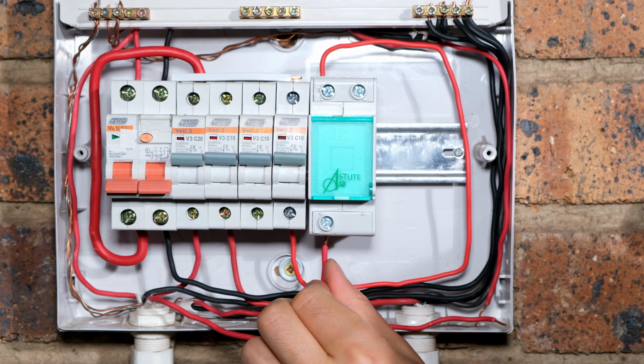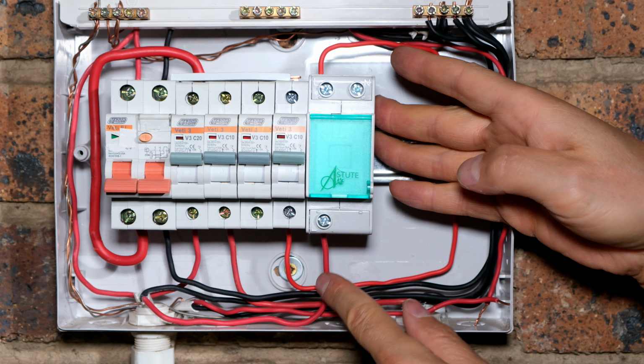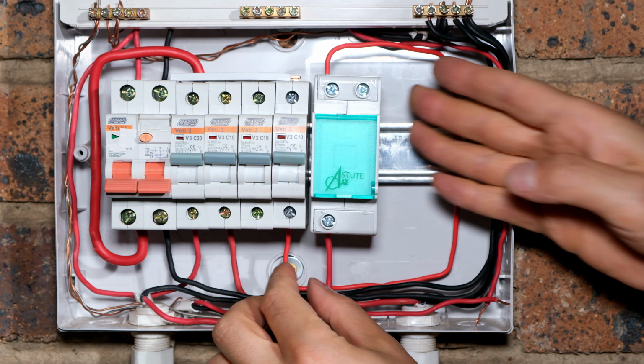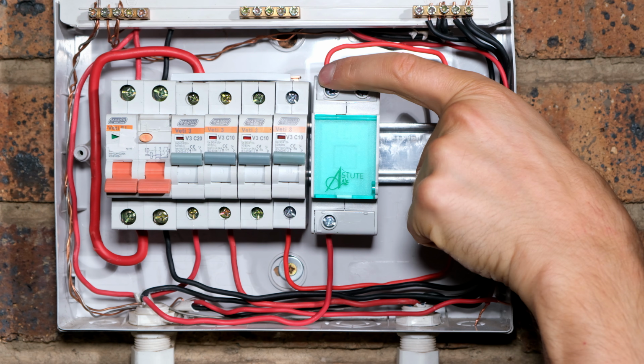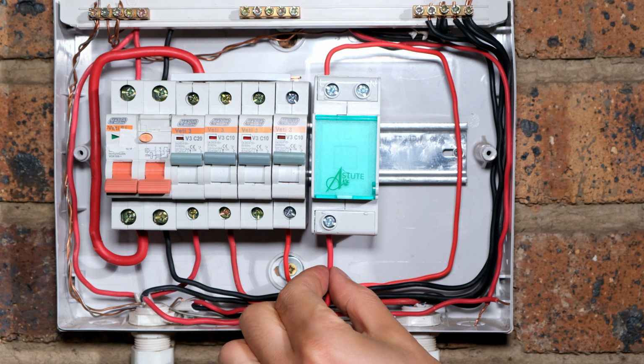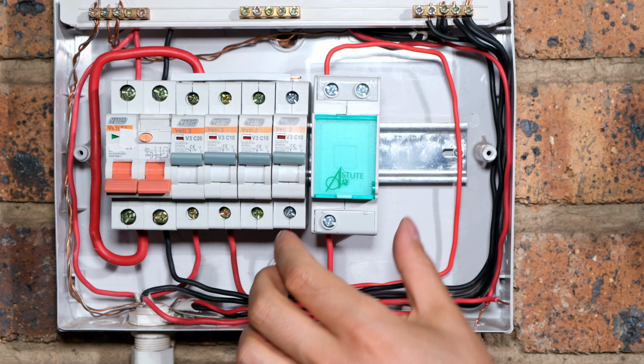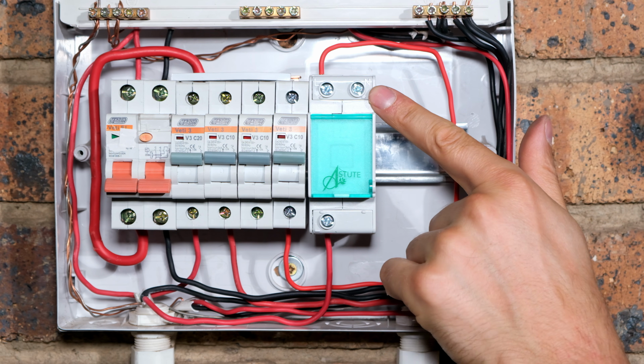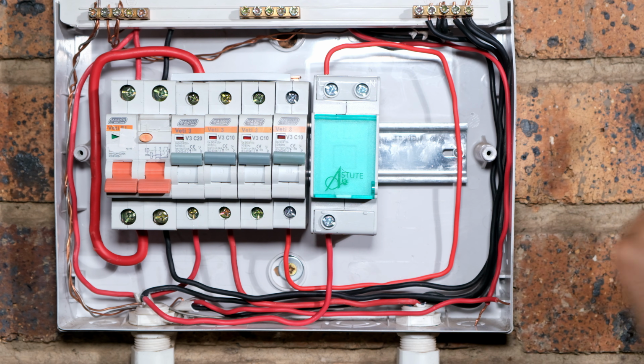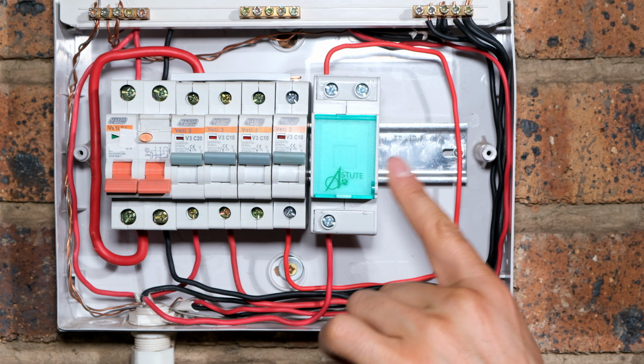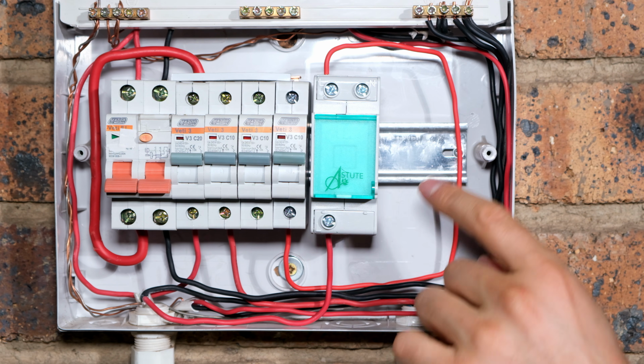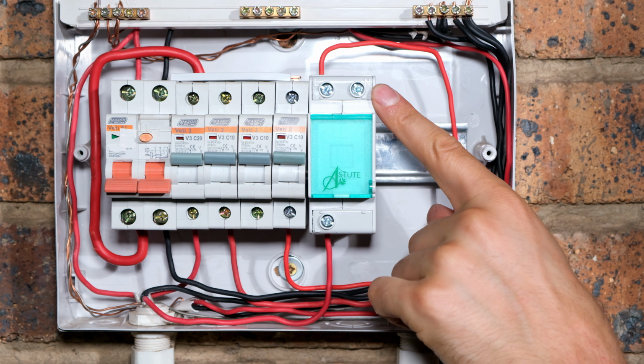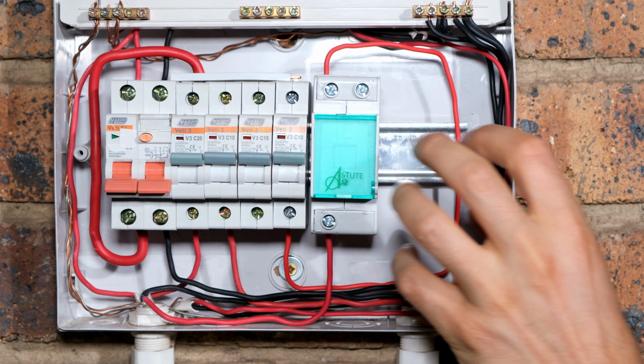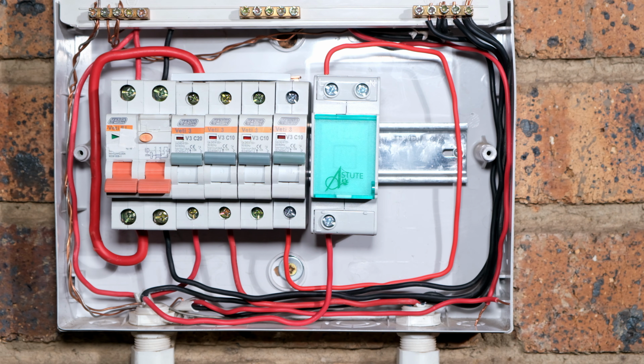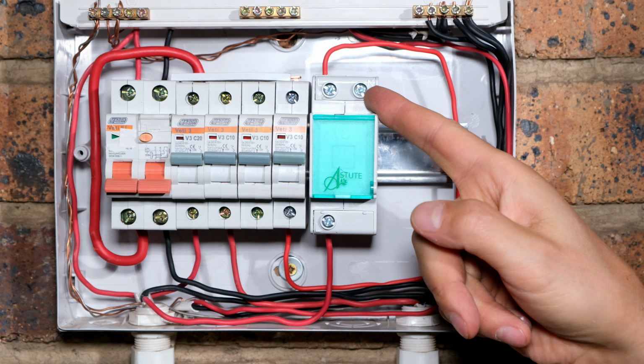So I'm going to go over here. Right, so there is my pool pump wire. So I'm going output of circuit breaker into live of timer, and then the output, which is the load wire, goes to my load, which is my pool pump. Now I need to connect one more wire, and that is the neutral, because the timer also needs power to work. Of course, it's an electronic circuit, so it needs a neutral wire to take a little bit of energy to operate the electronic circuit and the relay. So I need to connect a neutral wire from the end terminal over there.